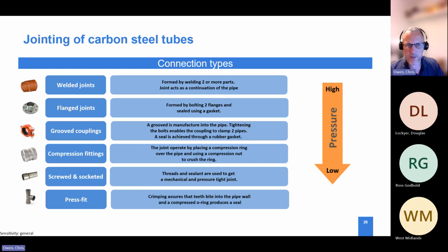As soon as you start dropping down to flange joints, you still get a good level of integrity, but it starts to fall off, and the further down you go, the more the pressure decreases in terms of suitability for both application operating pressures and test pressures. So when people look at pipework and do calculations on service life and pressure integrity, that's great, but the jointing will be the weakest link, and that needs to be taken into consideration as well.